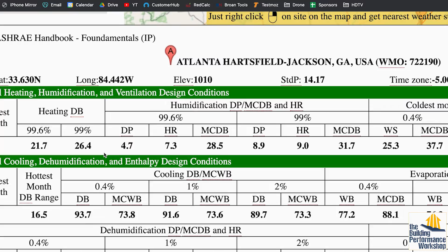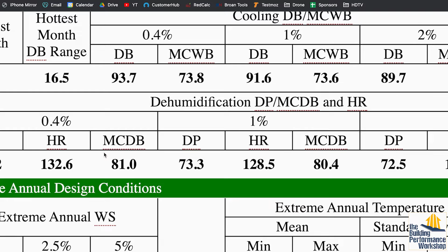It's the mean coincidental wet bulb because this is typically what the wet bulb is when it's at this temperature—so it's literally the opposite: at those temperatures, this is what the humidity level is. But if you look in the next section down, it says dehumidification, and you'll see a dew point, because that's a very good way to measure the actual amount of moisture in the air. Wet bulb's kind of a weird way to do it, but it's relative to your dry bulb temperature.